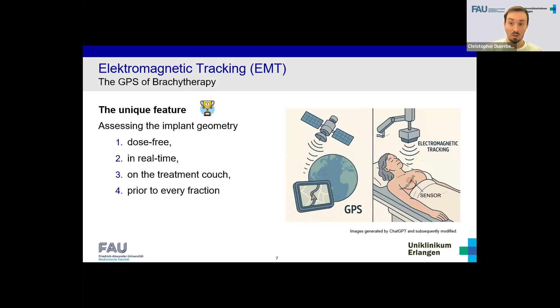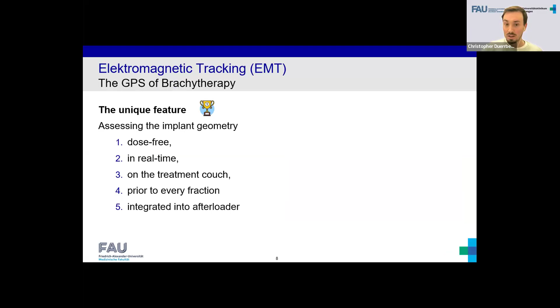And the big advantage of electromagnetic tracking is that it can assess the implant geometry dose-free and in real time on the treatment couch, so in patient treatment position and prior to every fraction. And this is something that no other technology is able to provide. And the even better thing is that in this project, this technology was integrated into a clinical afterloader. And we called that the hybrid treatment delivery system, because we were able to keep up the usual workflows, just with the addition of this electromagnetic tracking sensor that was integrated into the check cable.